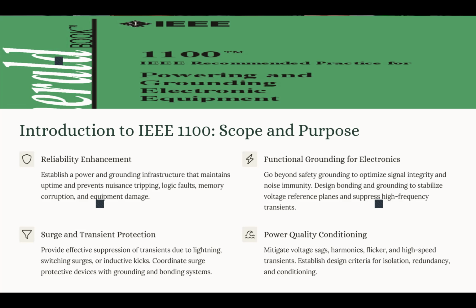So what are the solutions? The solution that IEEE 1100 recommends is to have isolation transformers, redundant feeders, UPS systems and harmonic filters. So we could basically mitigate those issues and provide high quality power for our sensitive electronic systems.